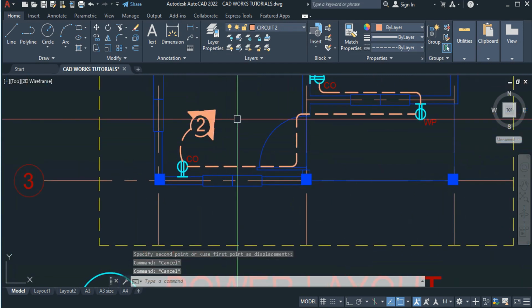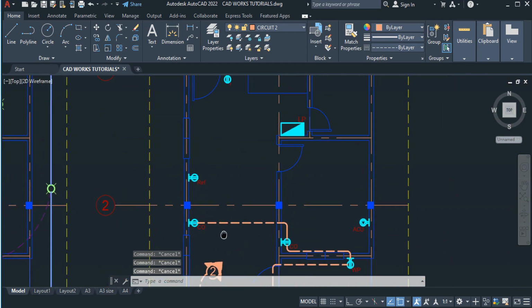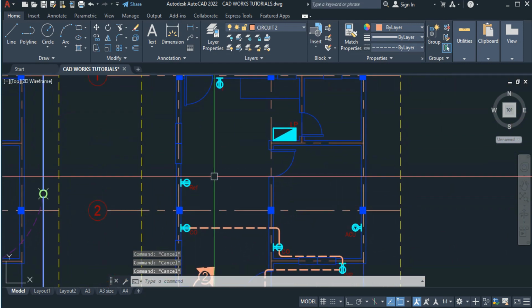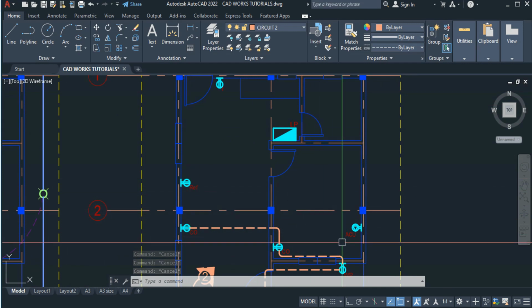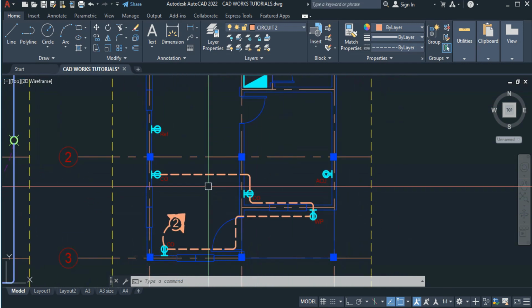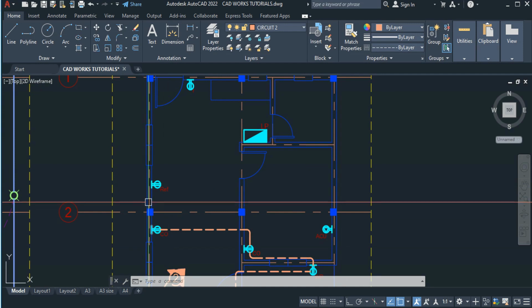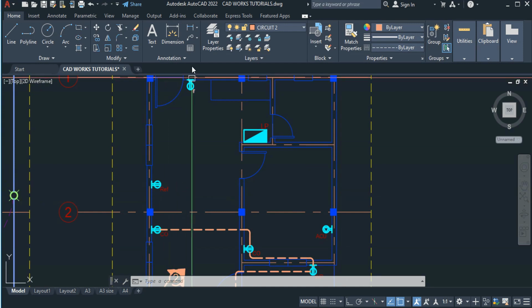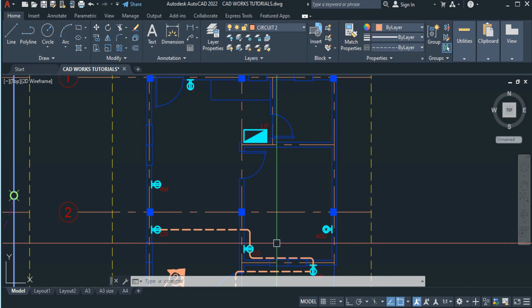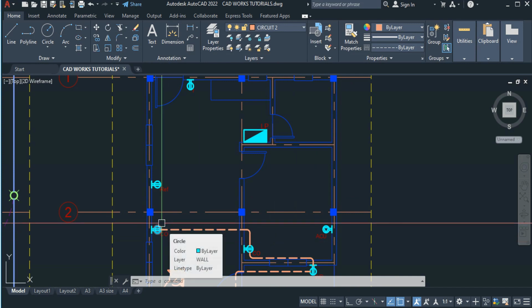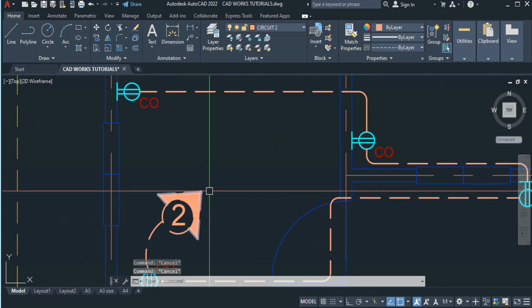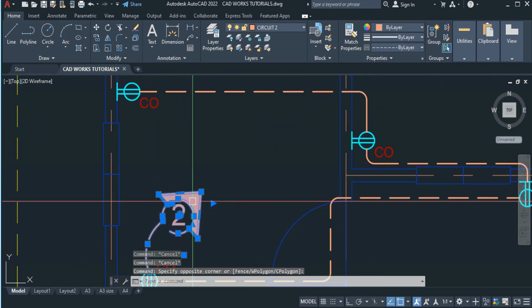Okay, so once you already have the circuit 2, it's time for us to place also yung circuit 3. So either you decide circuit 3, circuit 4, circuit 5. Now, the reason why I did not put them in one line only, because possible na mas malakas kumain ng kuryente ang mga ref, range, and lalo na yung ACU. So they need to have their own breaker, or what we call their own circuit. So mas maganda siya kung ganun ang paggawa. Okay?